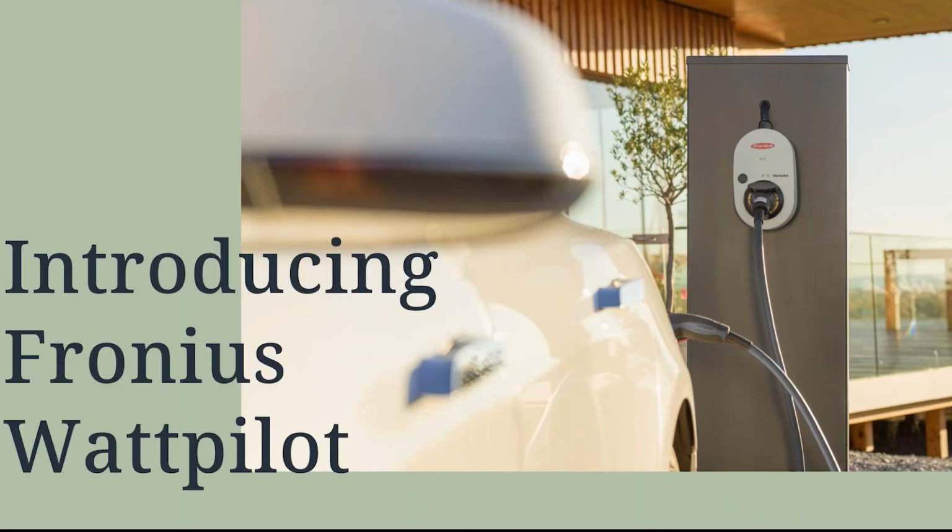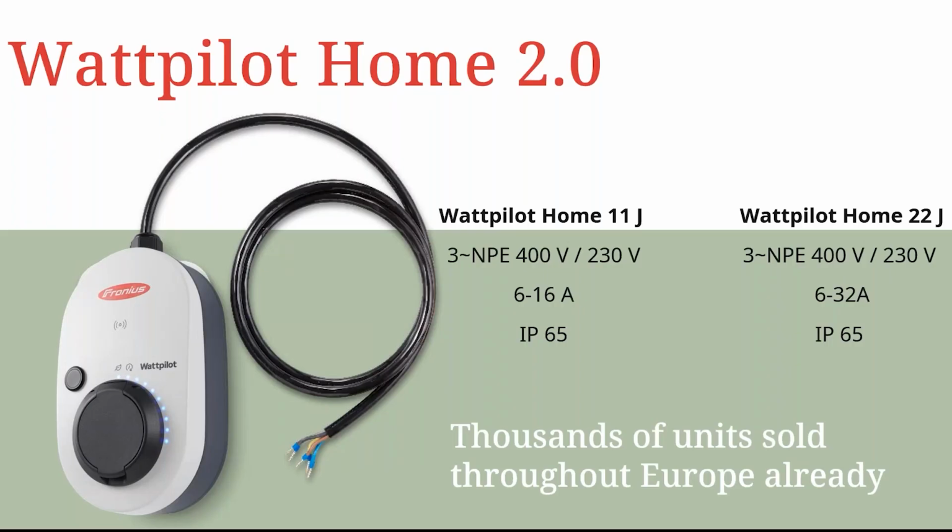So let's have a look at the Fronius Wattpilot variants that are available. The Wattpilot Home 2.0 is the unit that's currently on the market, and there are 2 versions. The 11J, which means maximum of 11 kilowatts power, 3-phase, and then the Wattpilot 22J, which is maximum 22 kilowatts power. They're both able to work in 3-phase or single-phase mode. The 11J has a maximum of 16 amps supply. The 22 has a maximum of 32. Both devices are IP65 rated.